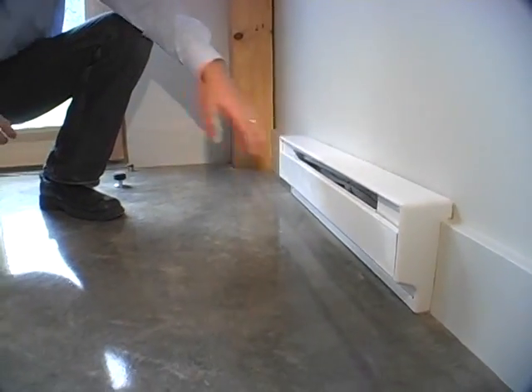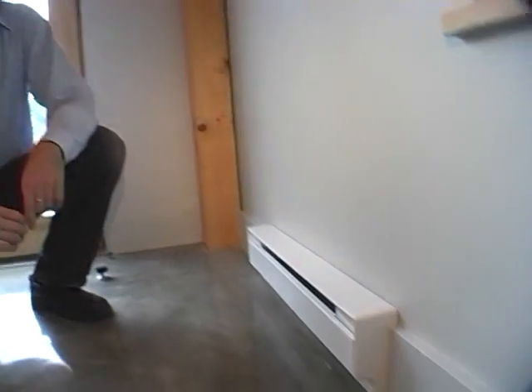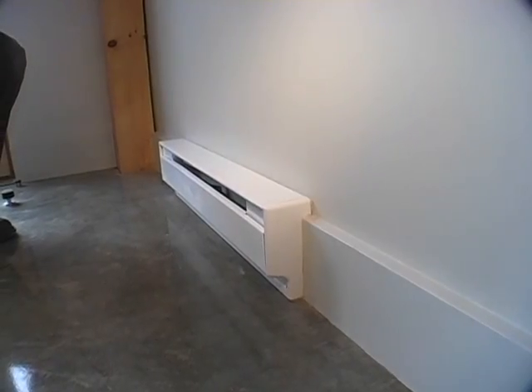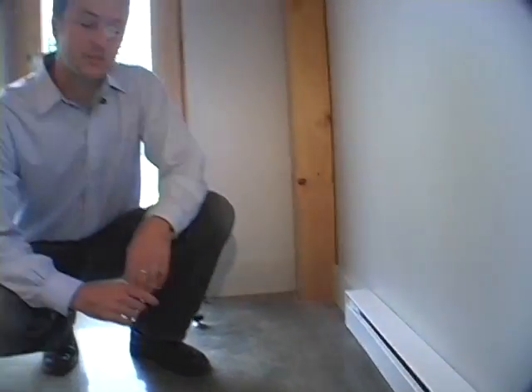Because we have such a low heat load, we can deliver it in many different ways using different fuel sources. In this case, we're using a very simple electric baseboard heater, here 2 feet for the living room, about standard issue in any bathroom. Because our heat loads are so small, electric heating becomes a very cost-effective system, both to heat the space and to install the mechanical systems, since electric baseboard heating is very inexpensive. So in construction, we're saving money by not paying for expensive heating systems. The whole heating system for this house cost about $500.